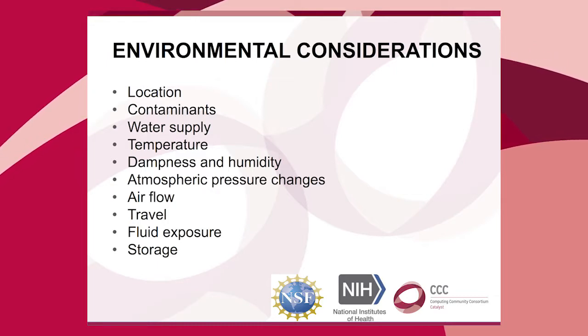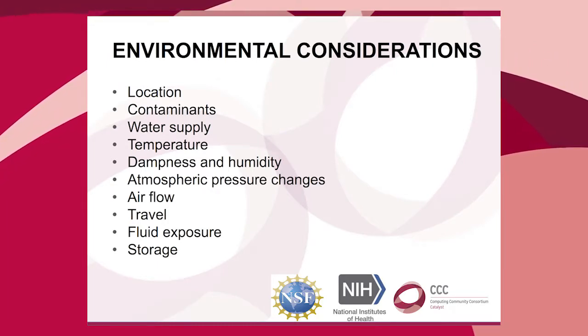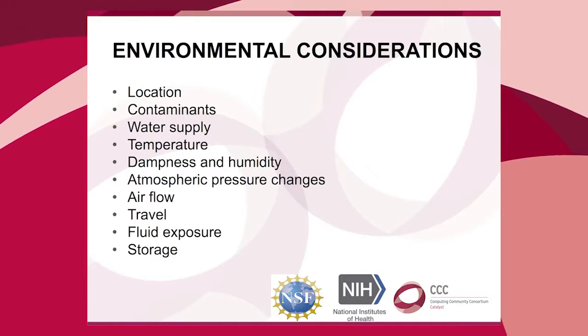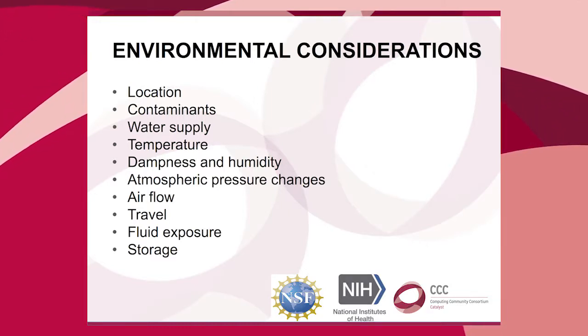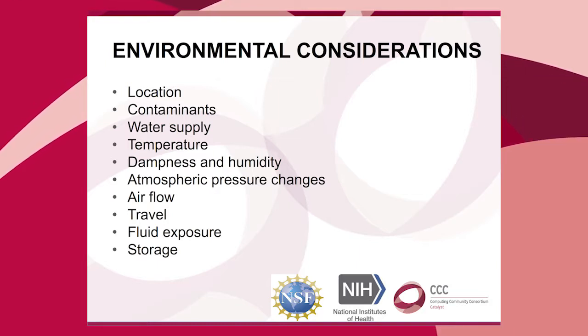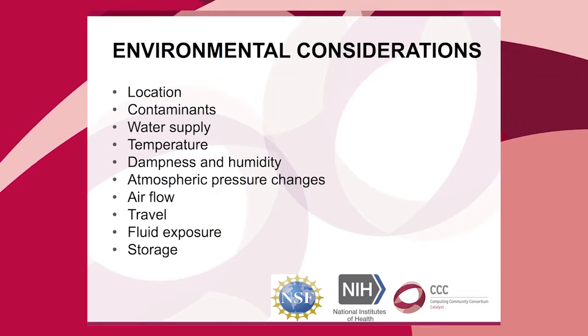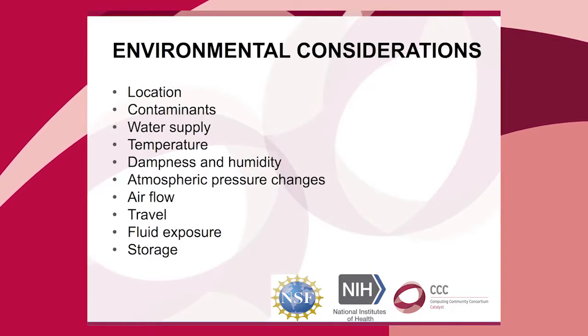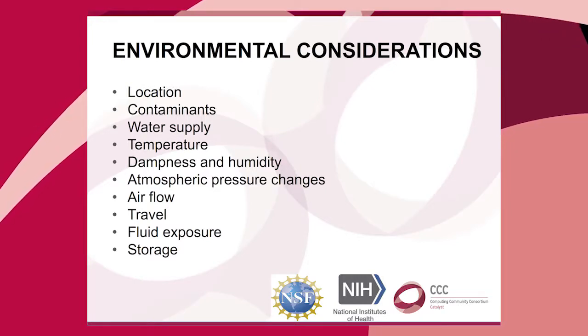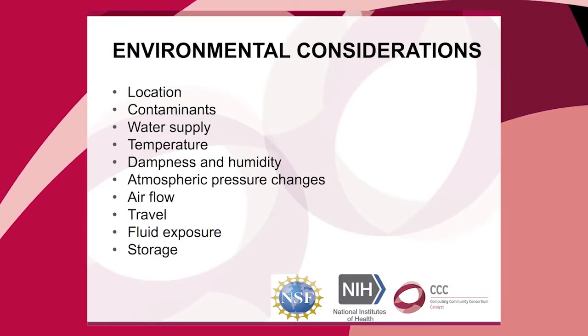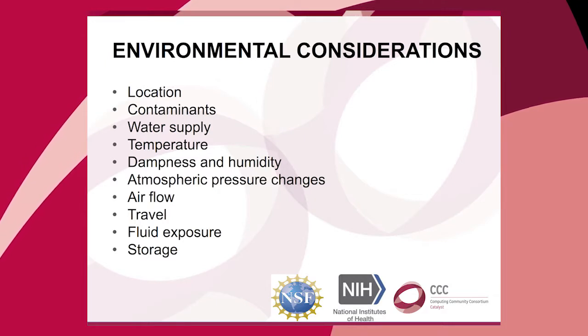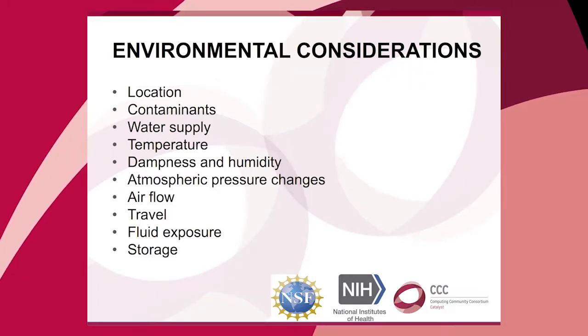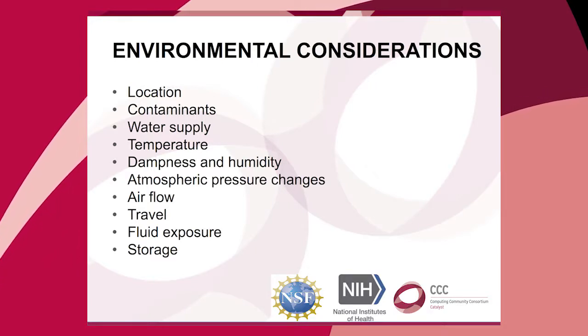Temperature changes: if somebody is living independently with their device, they're probably going in and out of warm rooms to very cool environments, and you could have a problem with condensation. So can your device continue to function with extreme temperature changes? Dampness and humidity: if it's too dry in the room, is there going to be a problem when you're operating your electrical equipment and there's static? This is something the manufacturer has to consider when designing their device.